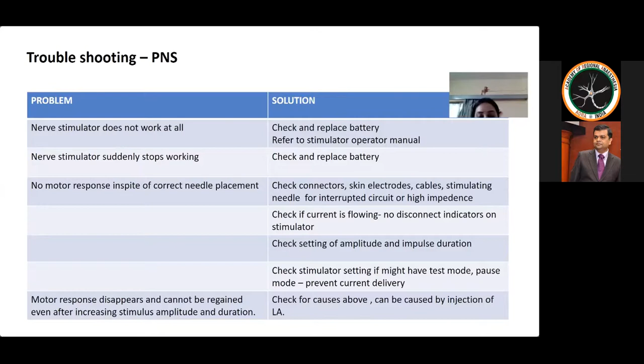We have to check the setting of the amplitude and impulse duration. We should also check whether the stimulator settings might have a test mode or pause mode, which will prevent the current delivery while performing a block. If the motor response disappears and cannot be regained even after increasing the stimulus amplitude and duration, then we have to check all the above parameters, and also sometimes by mistake they have injected local anesthetic, such a thing will happen.